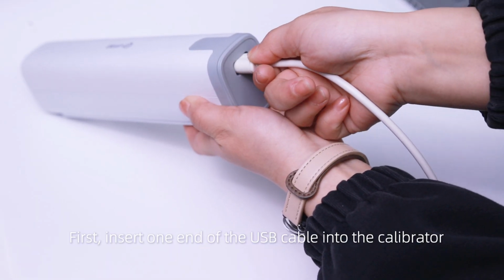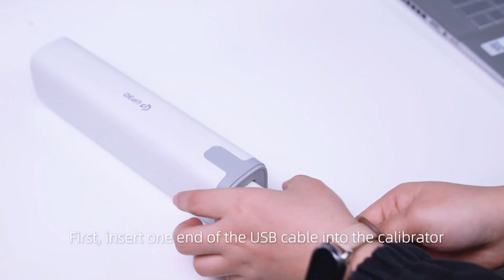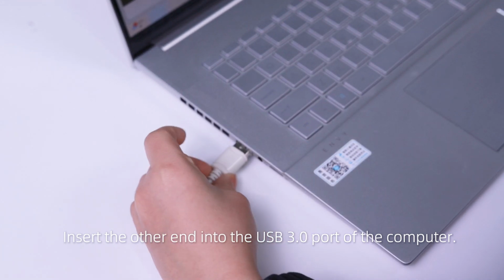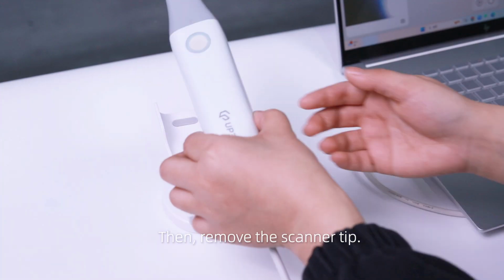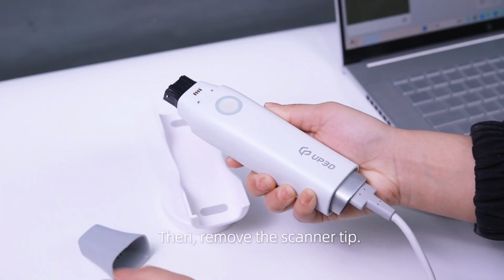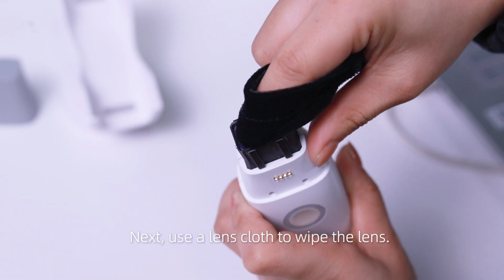First, insert one end of the USB cable into the calibrator. Insert the other end into the USB 3.0 port of the computer. Then, remove the scanner tip. Next, use a lens cloth to wipe the lens.